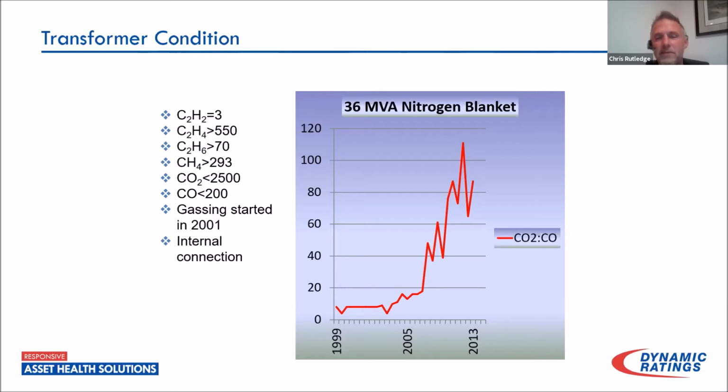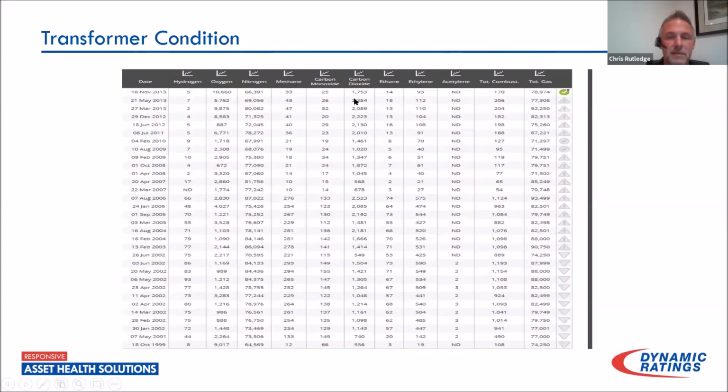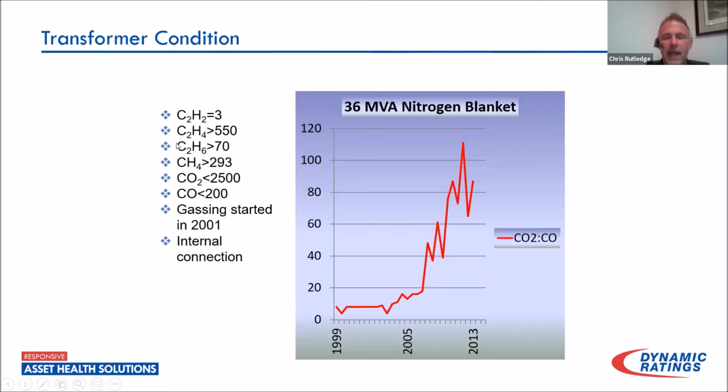So after going in this multiple times, actually went in somewhere around 2013, 2014, went in this unit and actually found that one of the NEMA pads on the low side had a loose connection. It had heated to the point that it was starting to cause some discoloration. We tightened it down. And again, this transformer is in service today. So that was 7 or 8 years ago.